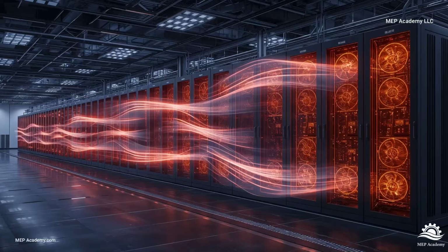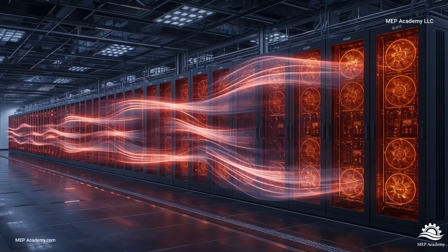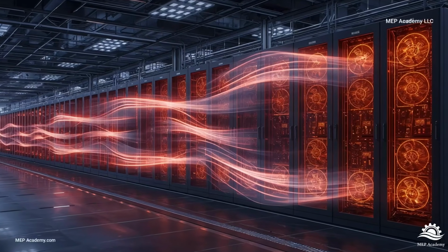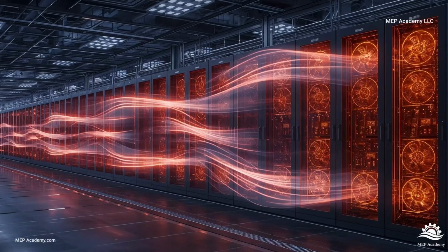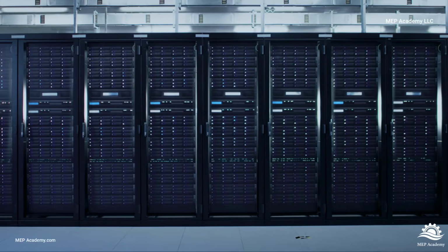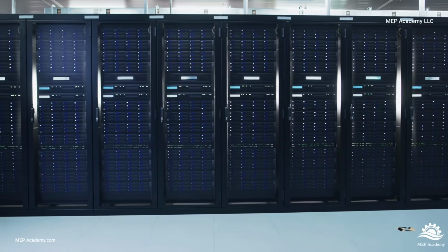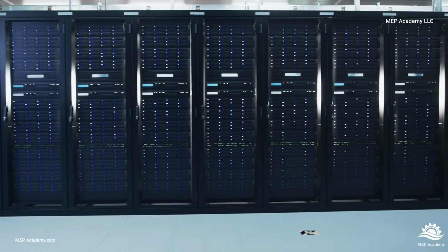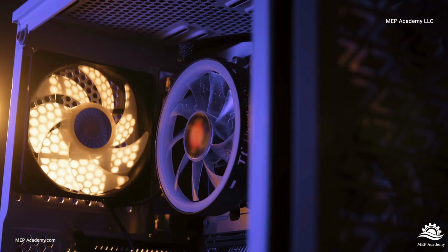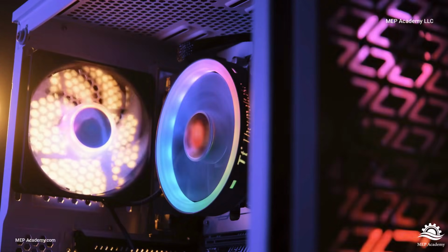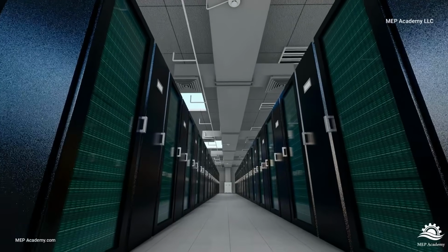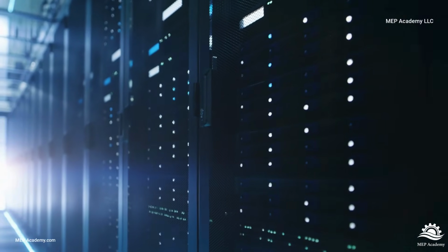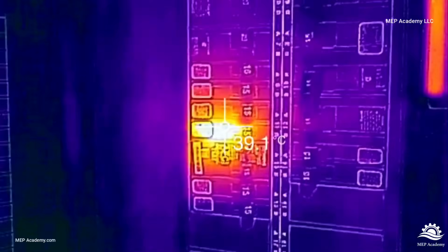Air is actually a poor heat transfer medium. It can carry heat away, but it requires very large volumes of airflow. As server densities increase, cooling systems must move more and more air through the rack. Fans become larger. Fan speeds increase. Power consumption rises. Noise levels increase. Eventually, there simply isn't enough airflow available to remove the heat efficiently.